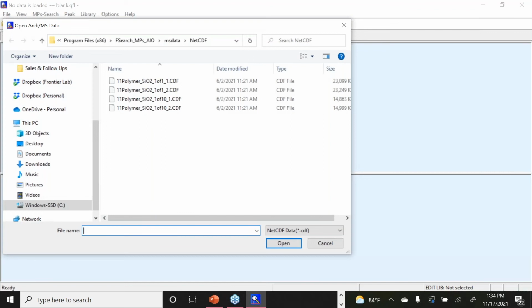So for demo purposes today, I am doing a 2-point calibration running with n equal 2, so 2 sets of each of my calibration points. Typically, you want to do 3 to 5 calibration points, but for the demo, I'm just going to show these 4 total runs. That was a 2-point calibration curve, and I was just using SiO2 standards. Again, depending on your target, you could have done CaCO3, so it doesn't matter really. I'm just showing the SiO2 here.